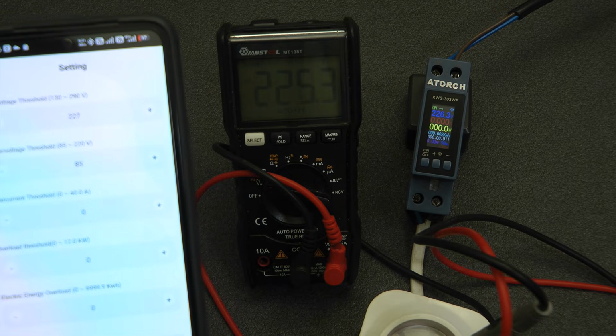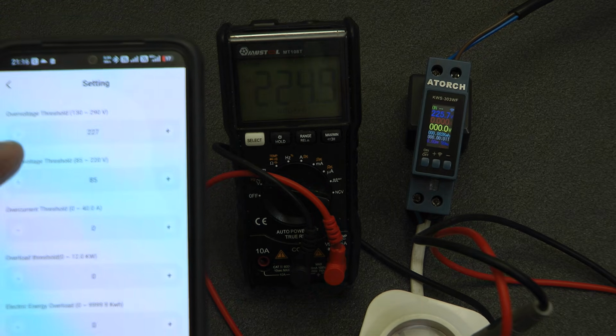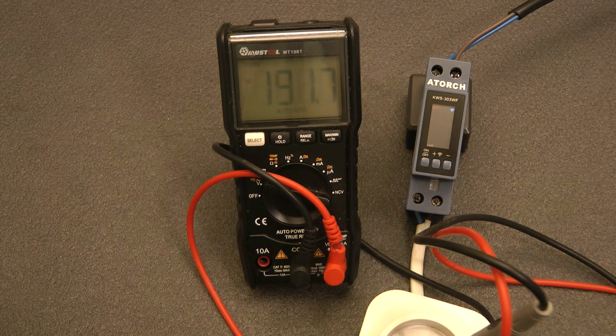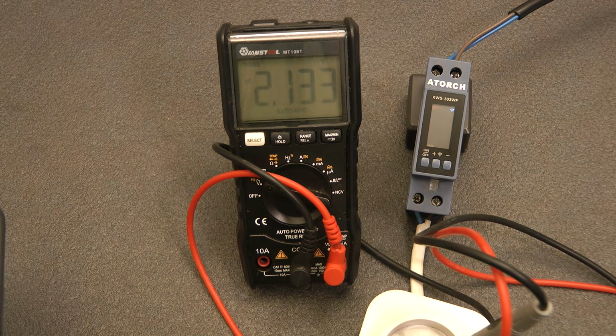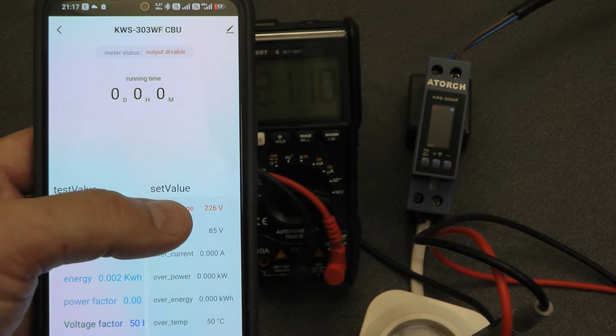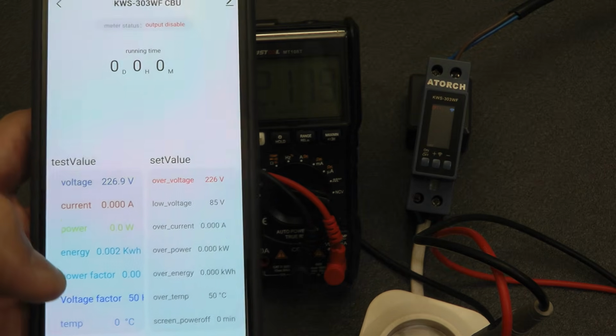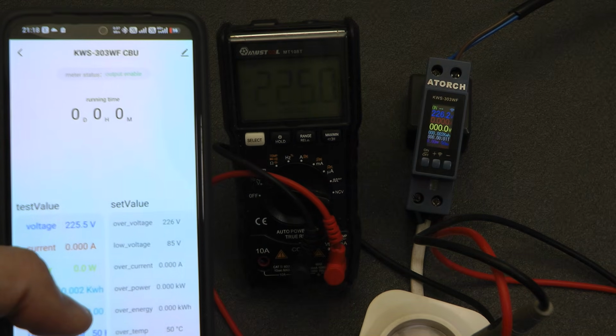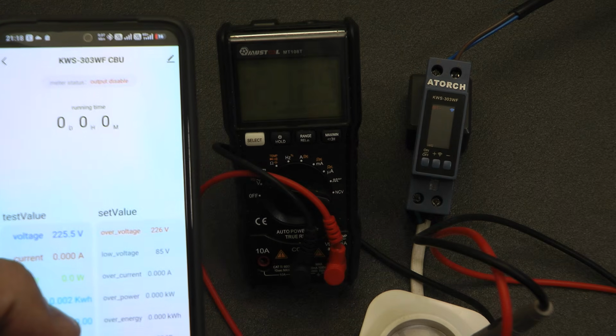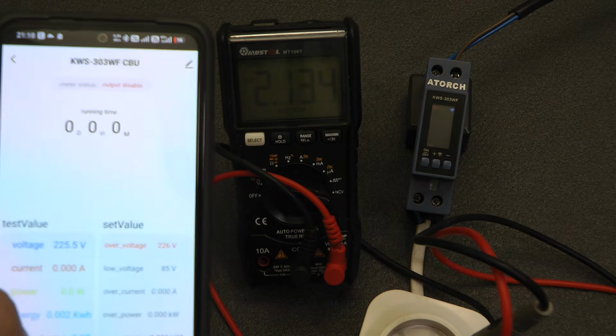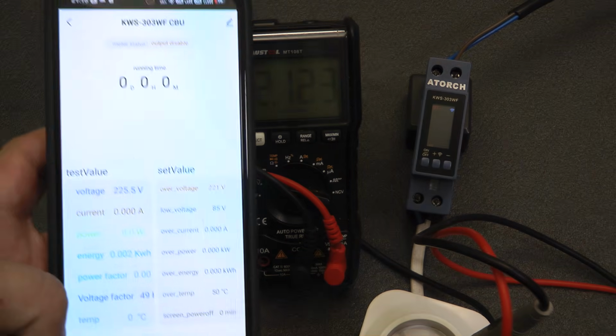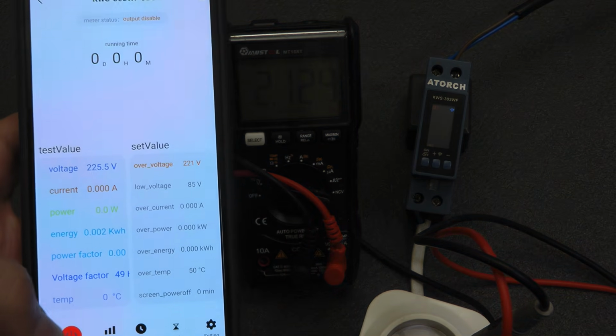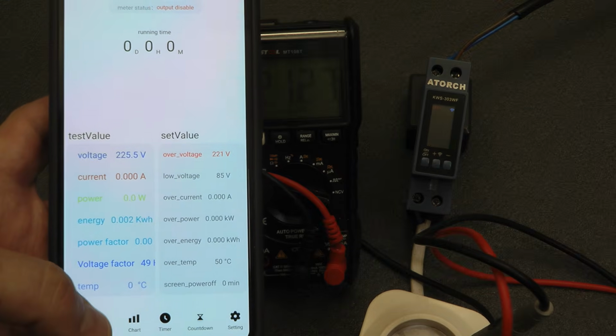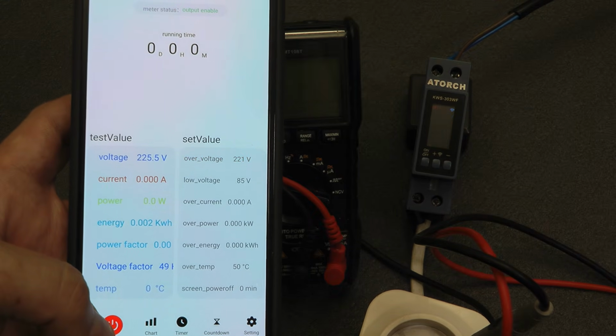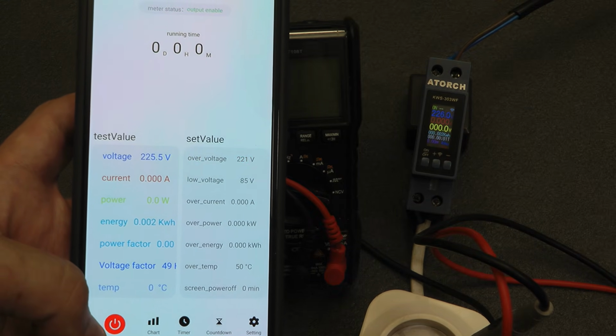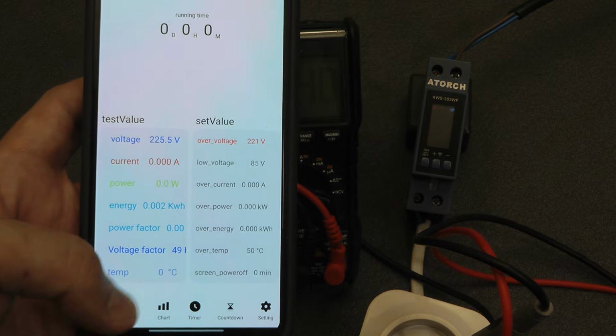Let's check the maximum voltage protection. I set the threshold to 226 volts. The threshold triggered, literally 2 seconds, and the relay switched off. In the app, the reason for shutdown is highlighted in red. In my case, this is overvoltage. Literally 2 seconds, 226 and 2, that is, 2 seconds, and the relay switched off. I will lower the protection threshold and set it to 221 volts, while the network is currently at 225. I try to switch it on. 2 seconds and the relay switches off, because the emergency threshold is still exceeded.